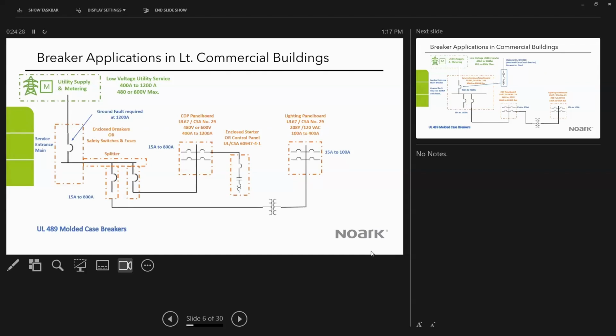Okay, so moving on, I'm going to run through some examples of different types of applications where breakers are applied, and I'm going to use buildings as an example, but these scenarios can apply to a machine that has a hierarchy of circuit protection requirements inside it. So in a light commercial building, so this is typically a very small warehouse, a small retail facility, strip malls, those kinds of locations.